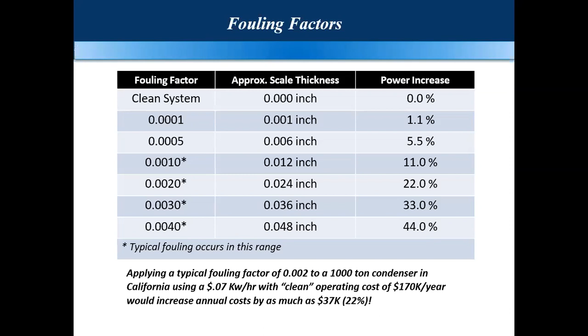That itself has an increase of 11% in power consumption. By power consumption, I mean that due to the increase in depositions, the heat transfer efficiencies are not what they are designed for. There will be films on the condenser tubes, maybe a coating on the pipelines. Those all reduce the heat transfer efficiency of the system, right? Based on that, your chiller approach is increasing slowly, and so the power consumption: the chiller condenser side has to do more work to cool down that amount of water in the required time. That is being expended with this power increase.